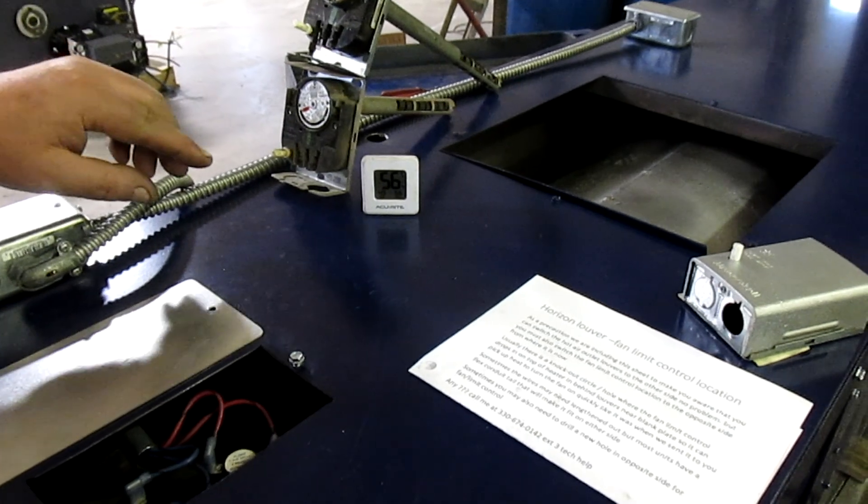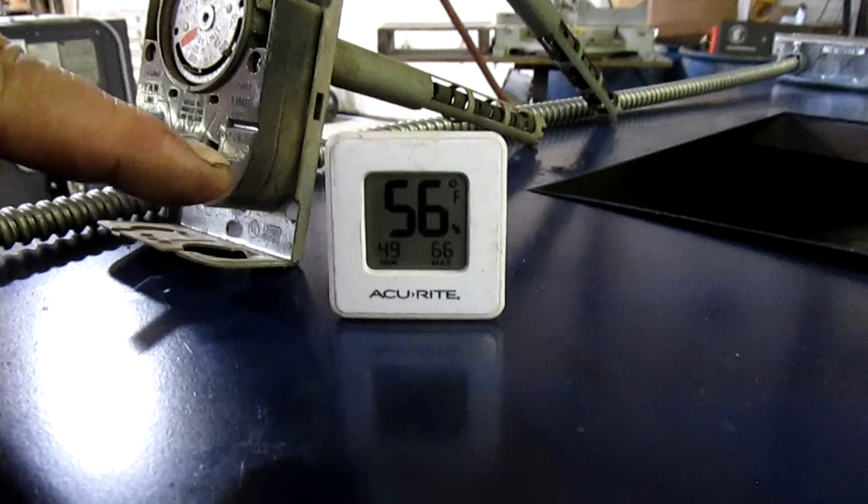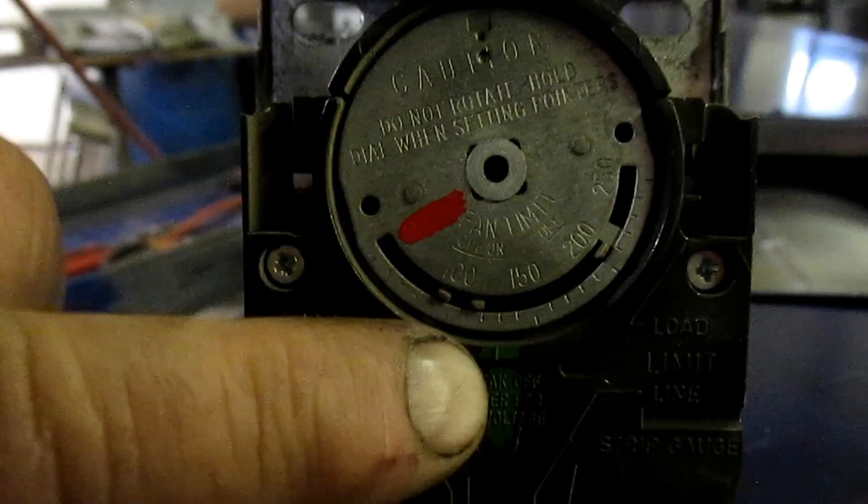Now let's take a look here, how we do this Triple Watchdog System and why we do it. Notice the temperature in the shop is 56 degrees. Here's an original fan limit control that's way too warm, and right here is the calibration line.